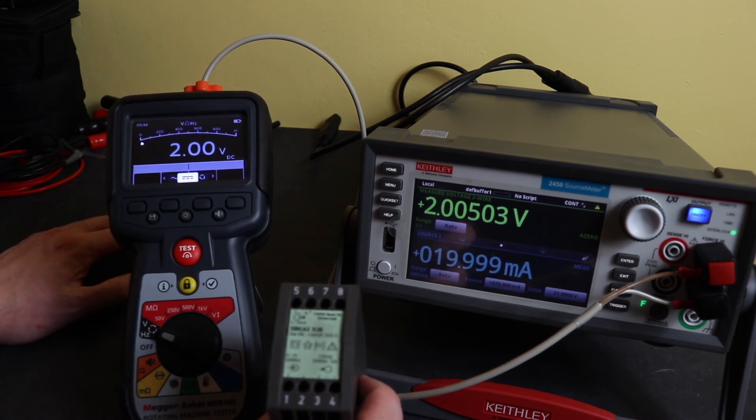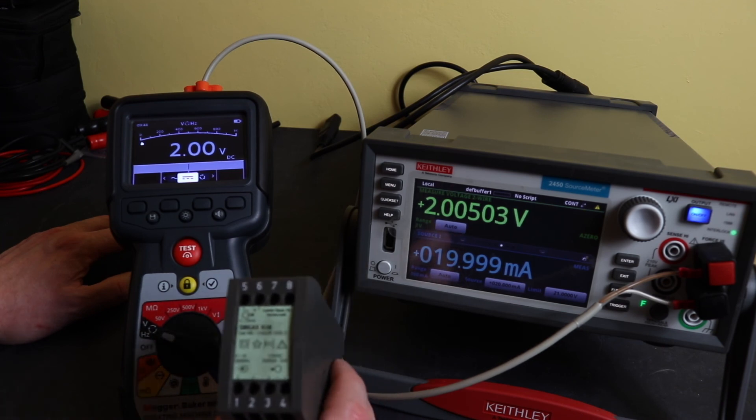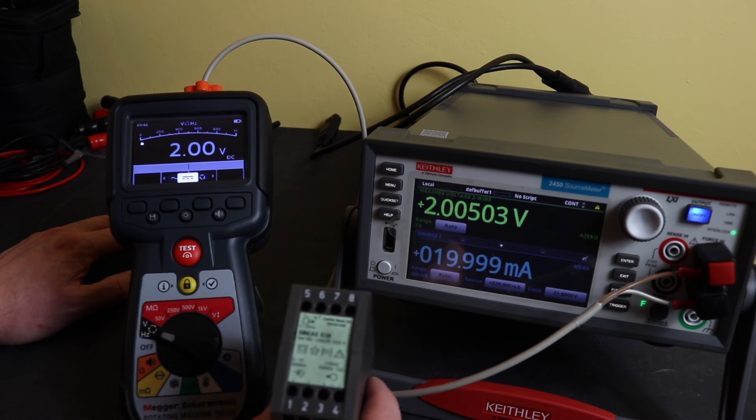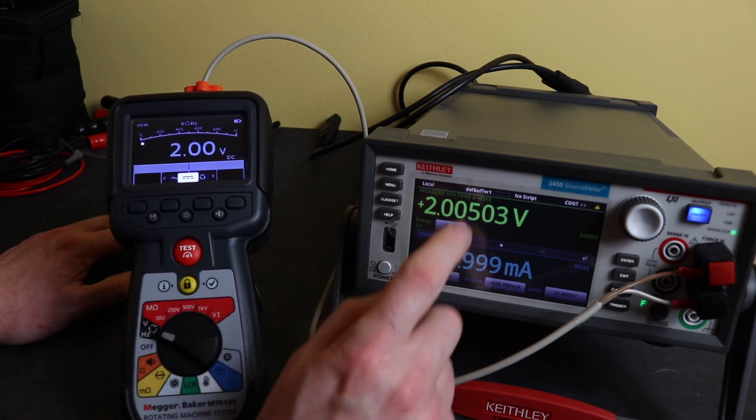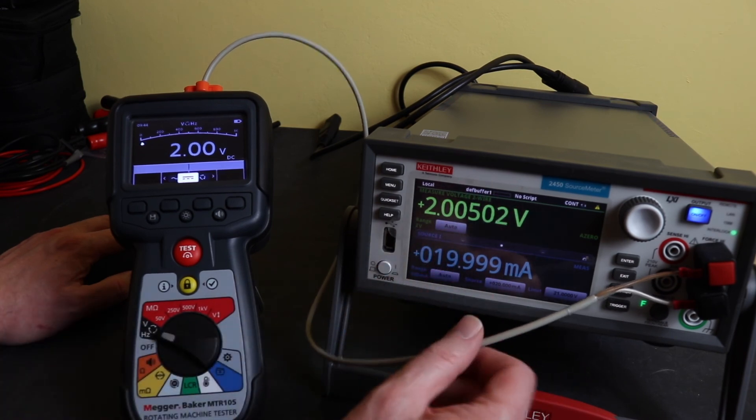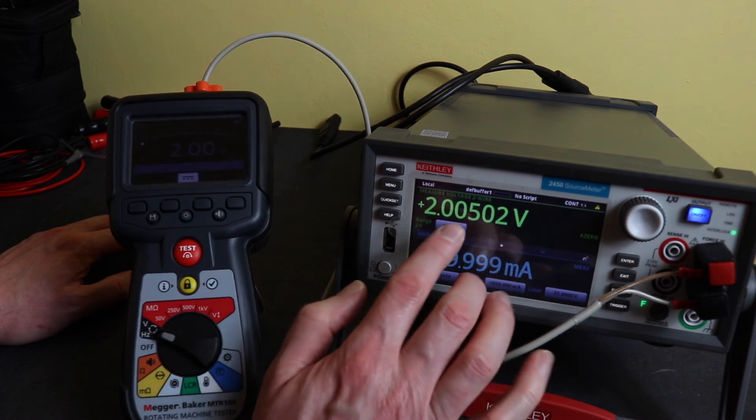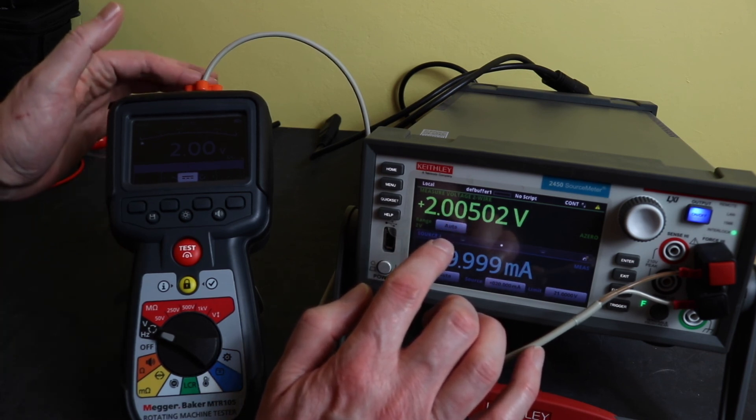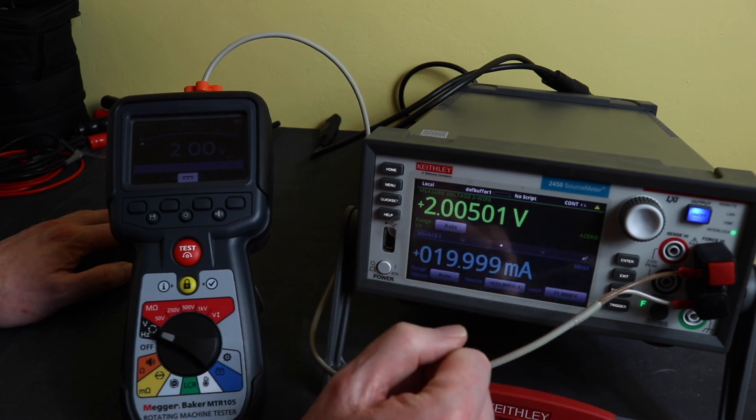Usually it's somewhere around about 500 to 750 ohms in my experience so by selecting the 100 ohms I hope to stay underneath that burden because the burden would be increased with the 100 ohms from this plus the input impedance of the control system plus any cabling resistance of any cabling in between the two which is what you see a little bit on here. Obviously I've got a little bit of resistance in this cable so instead of this being exactly on 2.00 volts which would be represented of that 100 ohm resistor there I've also got a little bit of cable resistance here including it which is giving my slightly larger voltage.